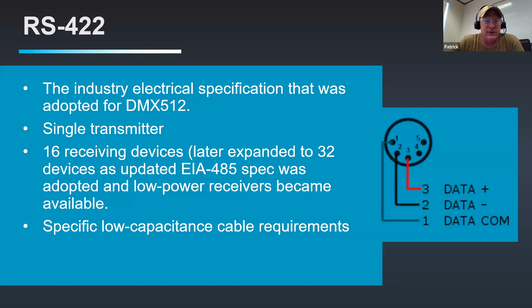And this is why it matters. Part of the protocol requires that the cable be 22 gauge, with a certain number of twists per foot, and a nominal impedance of 120 ohms. Where this becomes very important is when the signal goes out down the line, and when it gets to the end, it tries to turn around and come back. And if it turns around and comes back, now you've got signal flowing in both directions, and they can confuse the receiving devices. So we do what's called a termination at the end.